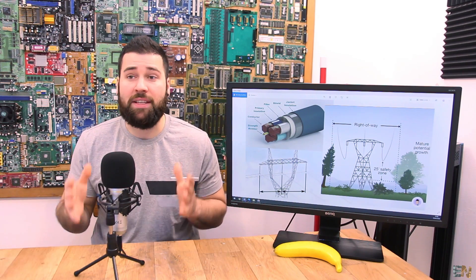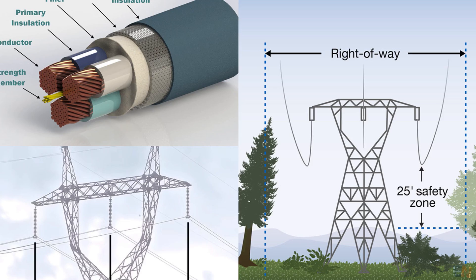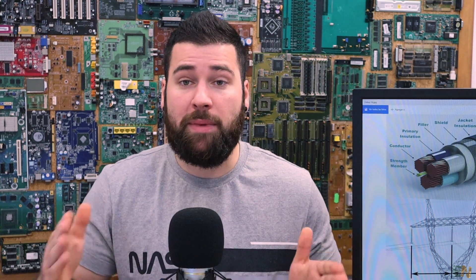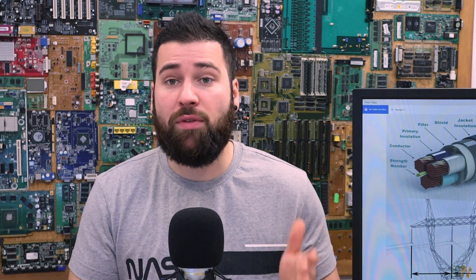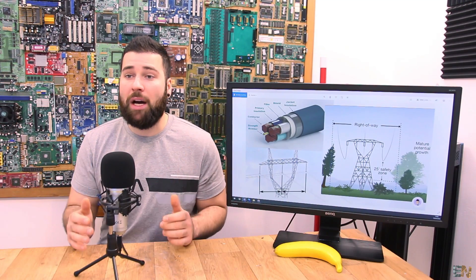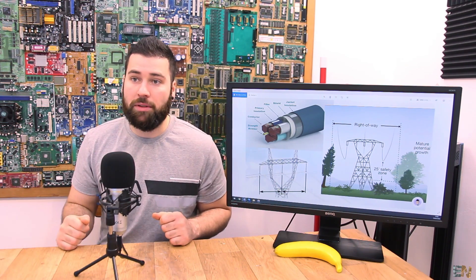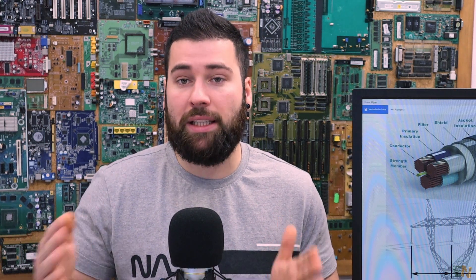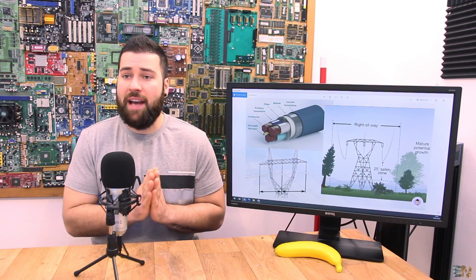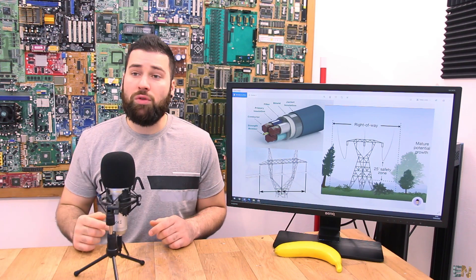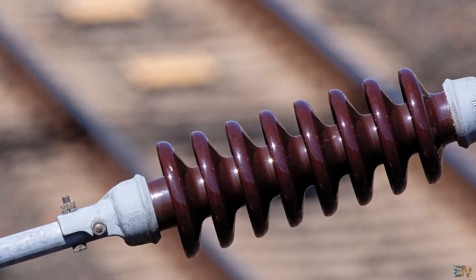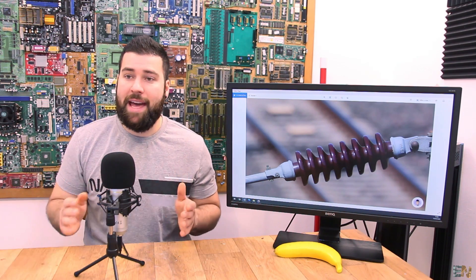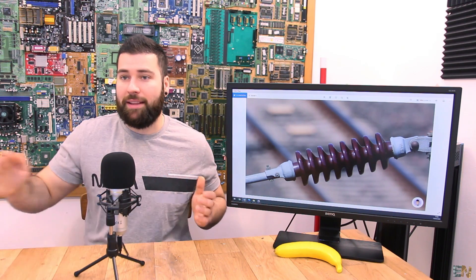Most of the wires on transmission lines don't have insulators because that would make them very thick, heavy, and expensive. Instead, engineers place the wires with bigger distance between them — this way we won't have discharges. The electrical towers are very big and tall to prevent discharges with anything on the ground. Air is a very good insulator, so large air gaps insulate the grid. We have a few meters between the wires of any high power line, and we also account for weather, since rain makes air more conductive. Closer to the metal tower, ceramic discs connect the wire to the tower to prevent electrical arcs. Interestingly, disc-shaped insulators are used instead of tubes because when it's raining, the superficial path of electricity is longer using a disc, helping avoid leakage.